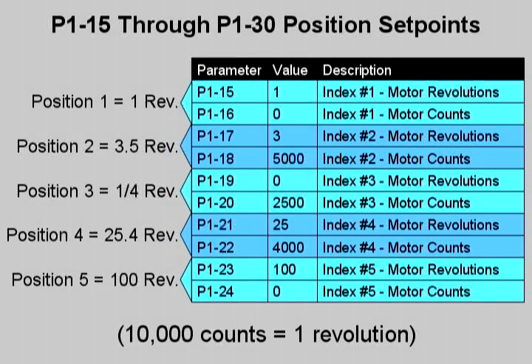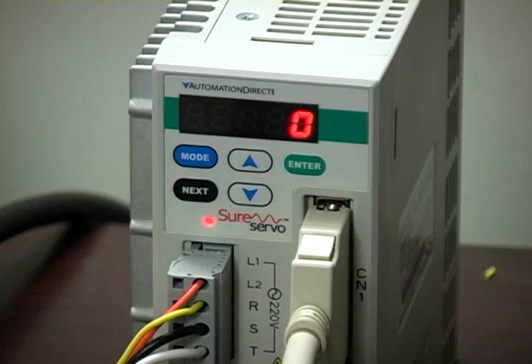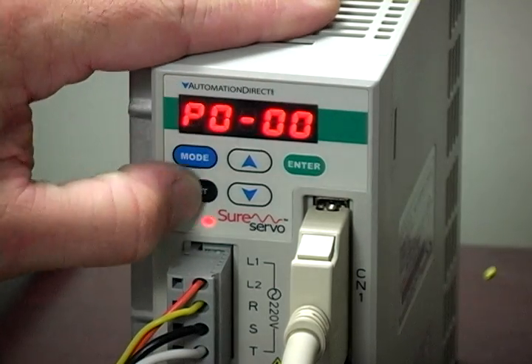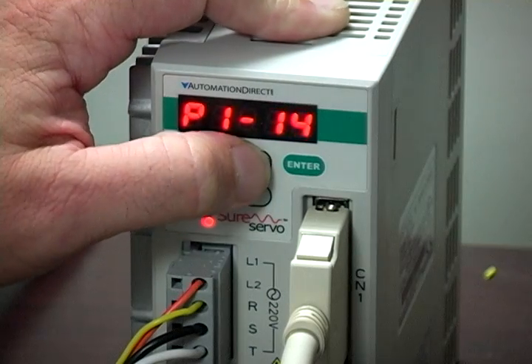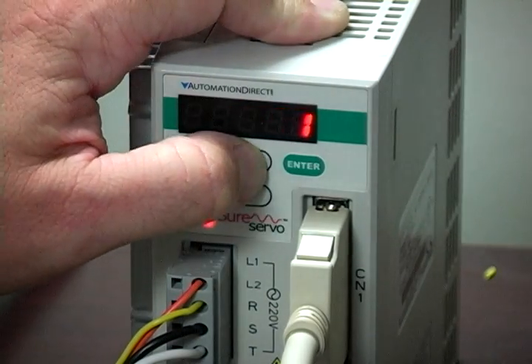Configuring the position set points. Parameters P115 through P130 determine the set points of positions 1 through positions 8. Each set point can have two parts: full motor revolutions in the first register and an additional number of pulses in the second. So to move the motor exactly one revolution, place a 1 in the first position parameter P115 and leave 0 in the second P116.